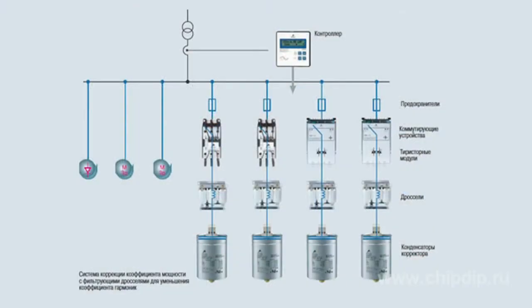Resonance can lead to occurrence of the following adverse effects: capacitor overload, transformer and distribution network overload, interference with measuring devices, control equipment, computers, resonant amplification of harmonics, and supply voltage deformation.